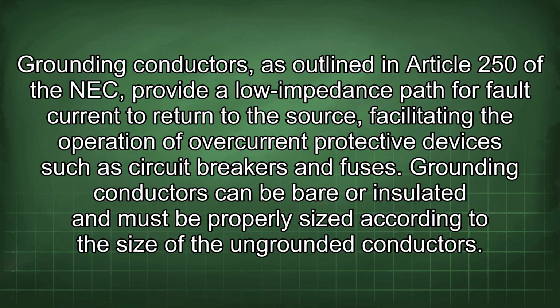Grounding conductors, as outlined in Article 250 of the NEC, provide a low impedance path for fault current to return to the source, facilitating the operation of overcurrent protective devices such as circuit breakers and fuses.